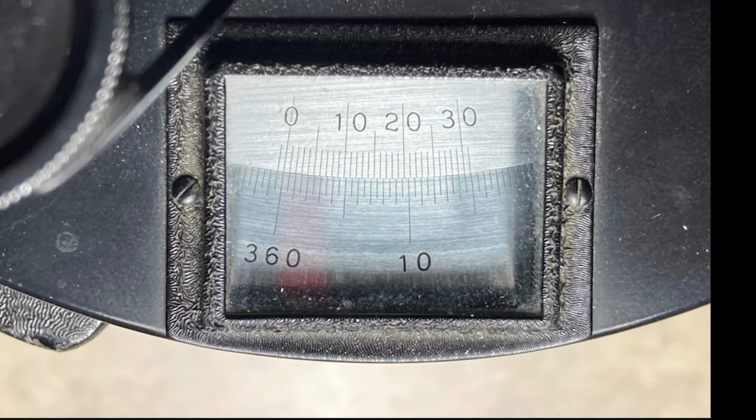On the left side of the spectrometer, you'll see a dial readout that's based on the vernier scale. We'll take a minute to describe that here. Notice that the 0 mark on the top scale is opposite the 360 mark on the bottom scale. The bottom scale is listed in degrees, with the next largest tick marks being 5 degrees, then single degrees, and then half-degree steps. The upper scale is in minutes, with 30 minutes per half degree, or 60 minutes per degree.